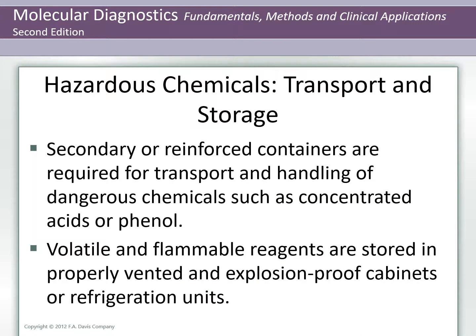Most reagents used in current molecular diagnostic methods are not hazardous, and the increased use of automated systems reduces exposure to reagents. But still, some manual procedures can present chemical hazards. Volatile and flammable reagents need to be stored in properly vented and explosion-proof cabinets or refrigeration units. Secondary or reinforced containers are required for transport and handling of dangerous chemicals, such as concentrated acids and phenol.